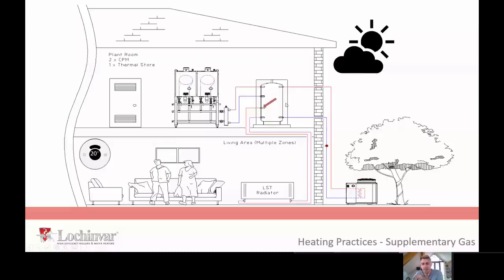We get a flow off to our building, goes off to the residents' care home, and it heats up their room to whatever their desired set point temperature is. The heat pump is capable of working to an outside air temperature of about 7 degrees in this application, because that's what gave them the equivalent carbon offset they needed from a hot water point of view, from a planning application point of view. And then what happens is, typically, because it's a care home, someone turns up the room thermostat, increasing the kilowatt loading on the building because your outside air temperature and your building temperature, big disparity in terms of the temperatures there all of a sudden.